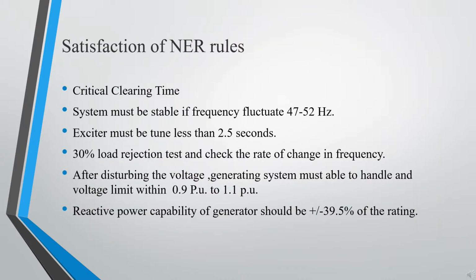Now I will cover the NER clauses that need to be satisfied for new generation. As per the NER clauses, we need to determine the critical clearing time and how it is affected by new generation. As per the NER clauses, CCT should not have an adverse effect on the new generation, and this is satisfied in our project. As per AEMO, the system must be stable in case of frequency disturbance within a range of 47 to 52 Hz.